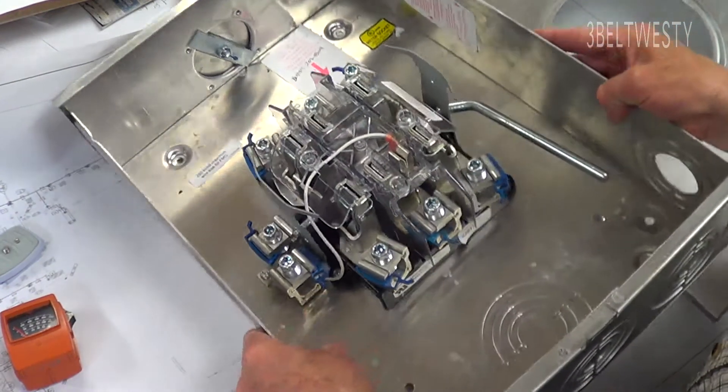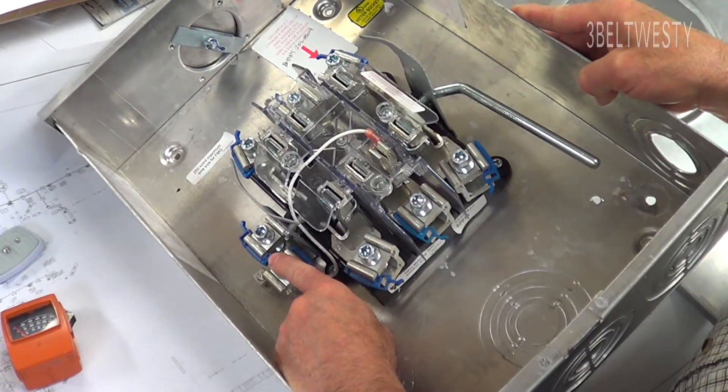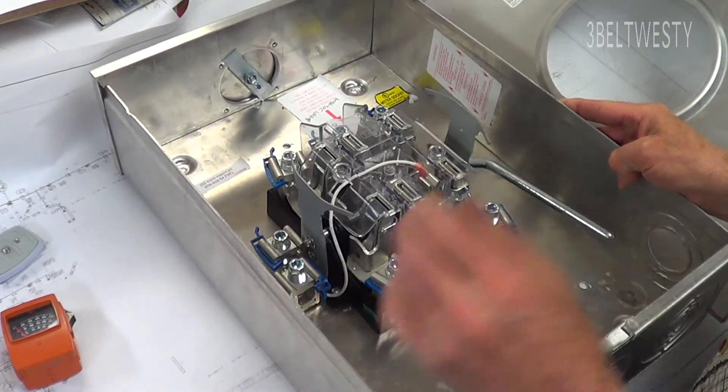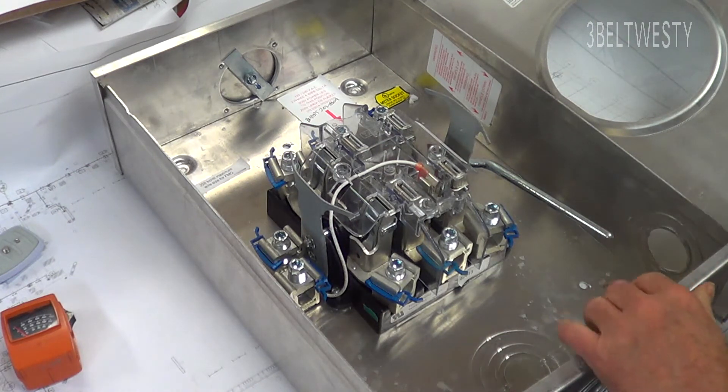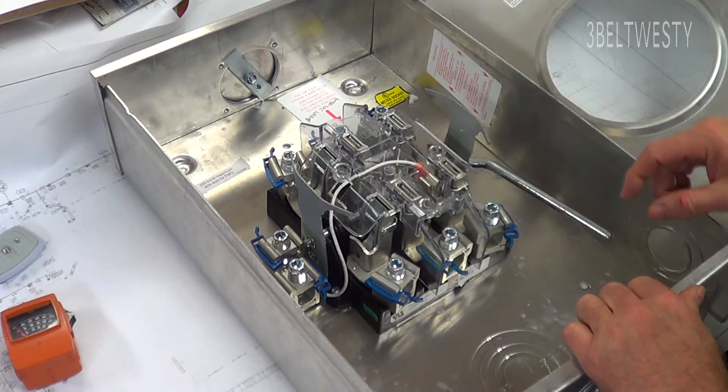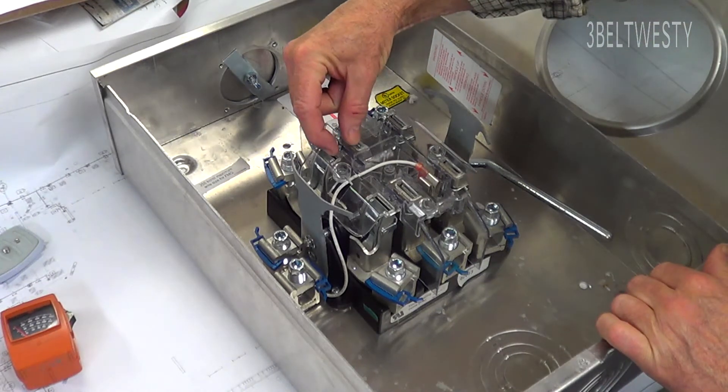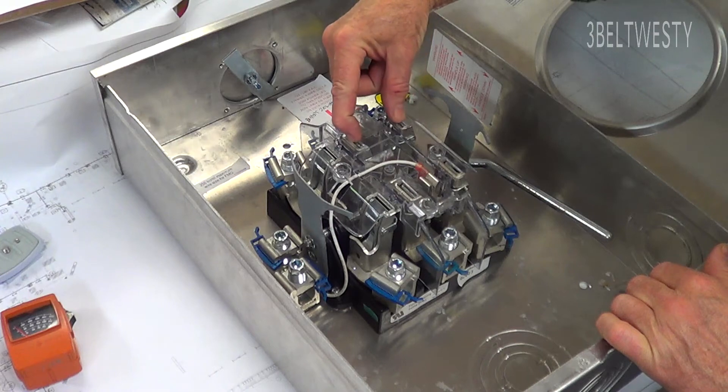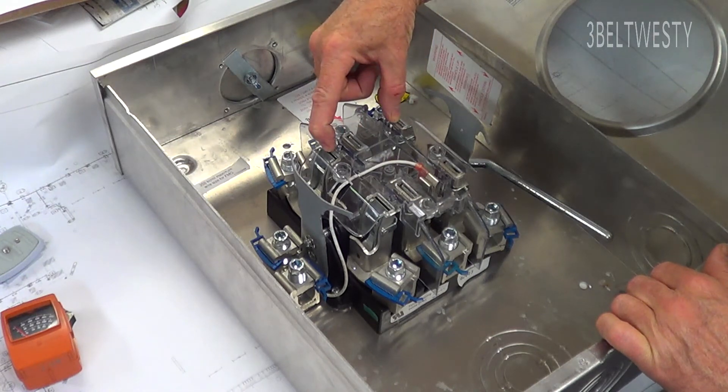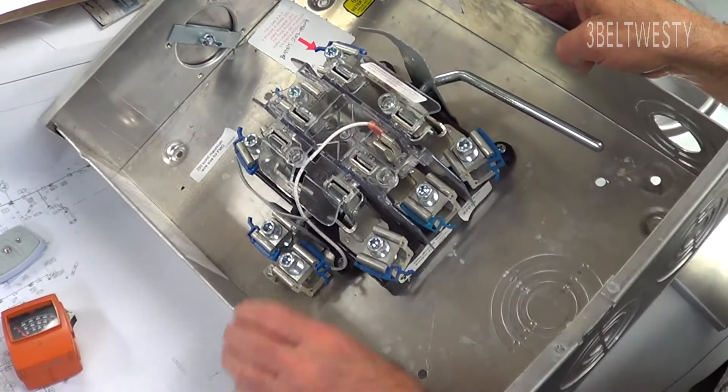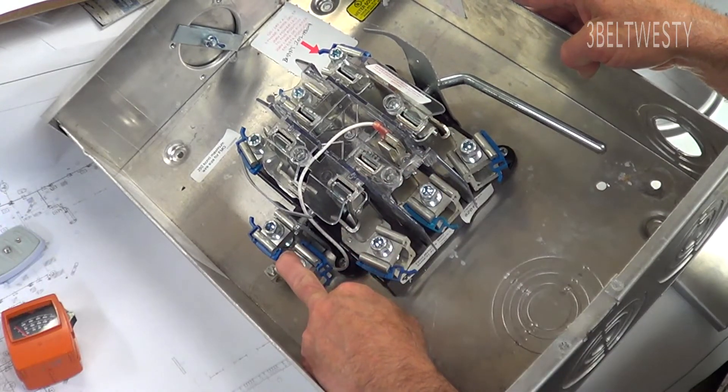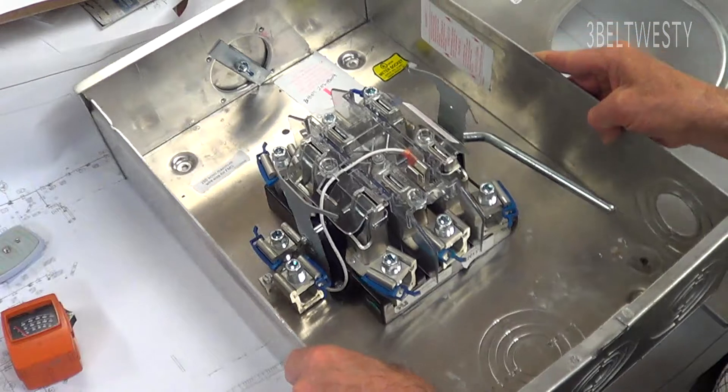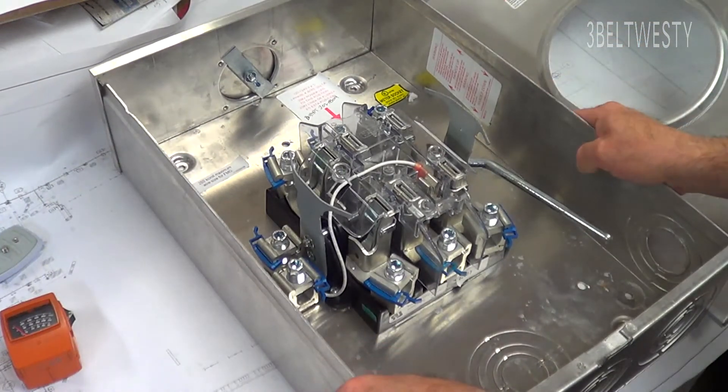Of course this is the neutral. Another configuration that's used is a higher voltage configuration where you have 277/480. That's where you've got 480 volts across here, 480 across here, 480 across here, and then you have 277 volts between each one of these three hots to the neutral.